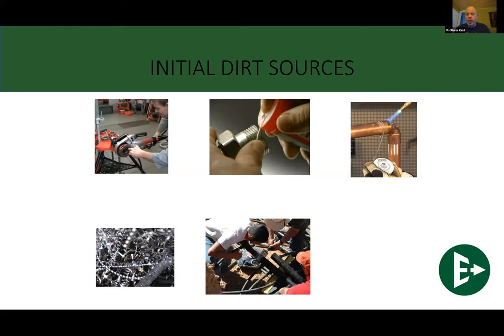If you're doing an HDPE system where you're fusing the pipe together, this, for example, is a geothermal system. I believe this one's in Chicago, where this picture was taken. But anyway, those little plastic filings that you get when you cut this pipe can let loose and get into these systems. It's not as common with fused systems, as when you fuse pipe together it usually melts those plastic fragments together, but it's not to say it's not possible. Not to mention, if you're doing any work outdoors, you do have to be cognizant of the fact that these pipes might be in the dirt and mud and stuff like that.